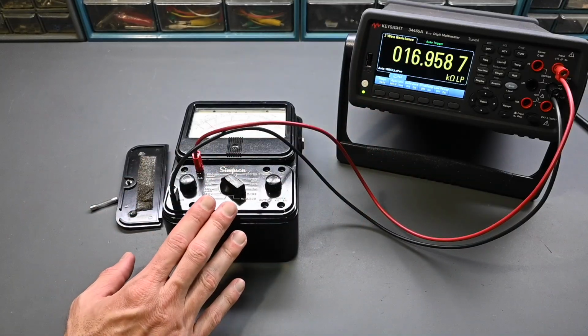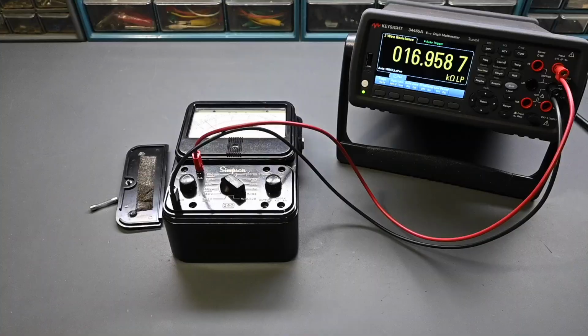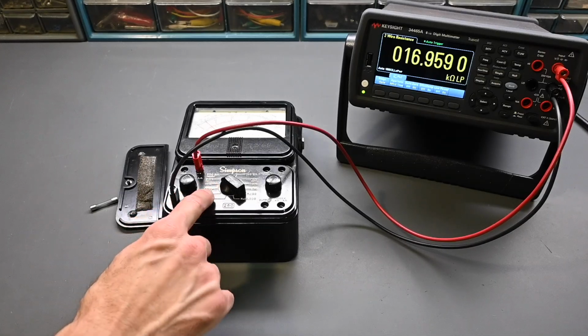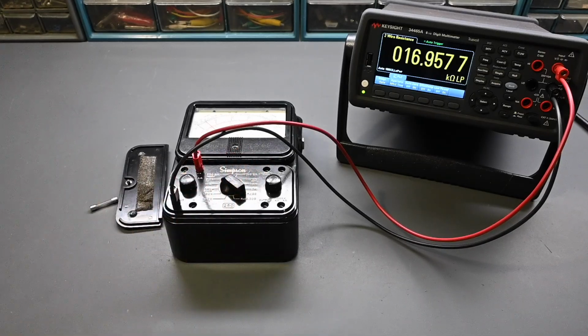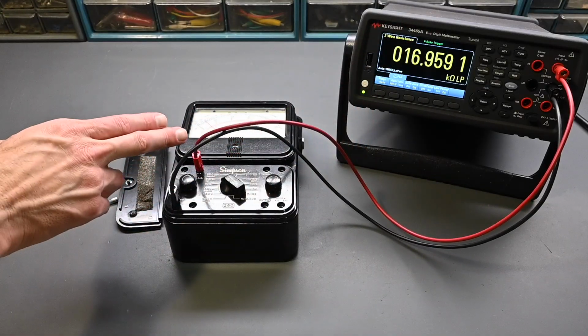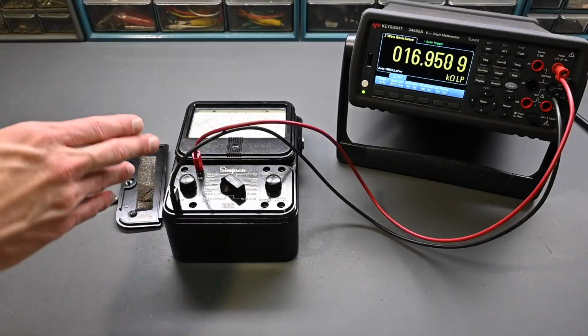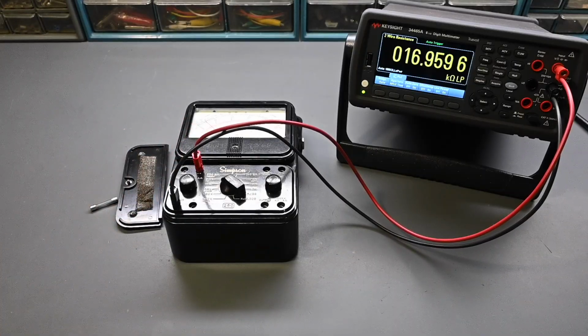This meter has a 20,000 ohms per volt rating on the DC measurement and 5,000 ohms per volt on AC. What does that mean? Basically, you just take the full scale reading, so in this case we're on the 1 volt full scale, and multiply that by 20,000 ohms. So 1 volt times 20,000 ohms is 20,000 ohms, and we're not getting that. That tells us there's a problem not only in the meter circuit, but perhaps elsewhere in some multiplier resistors. We're starting to see some other issues going on here.